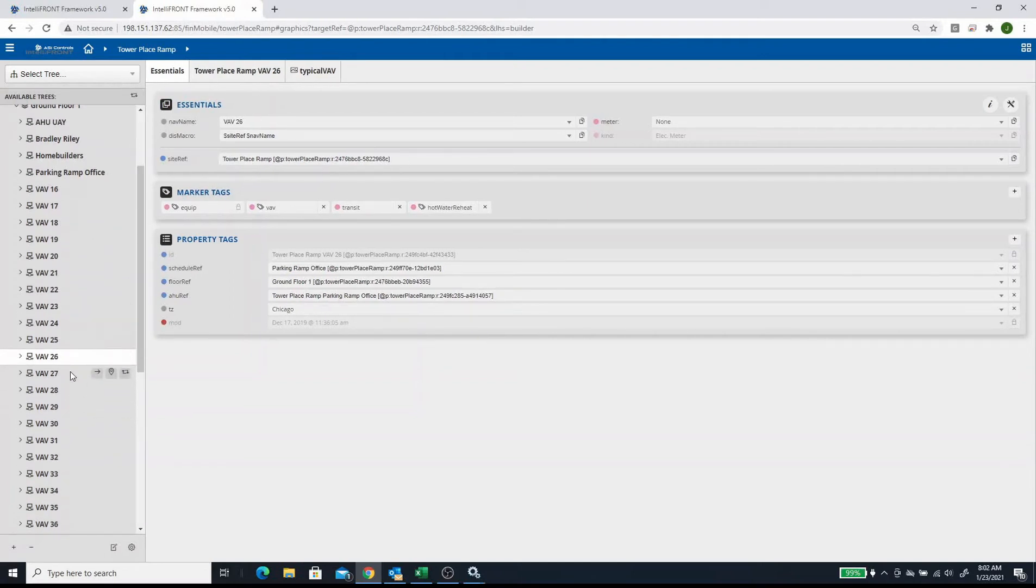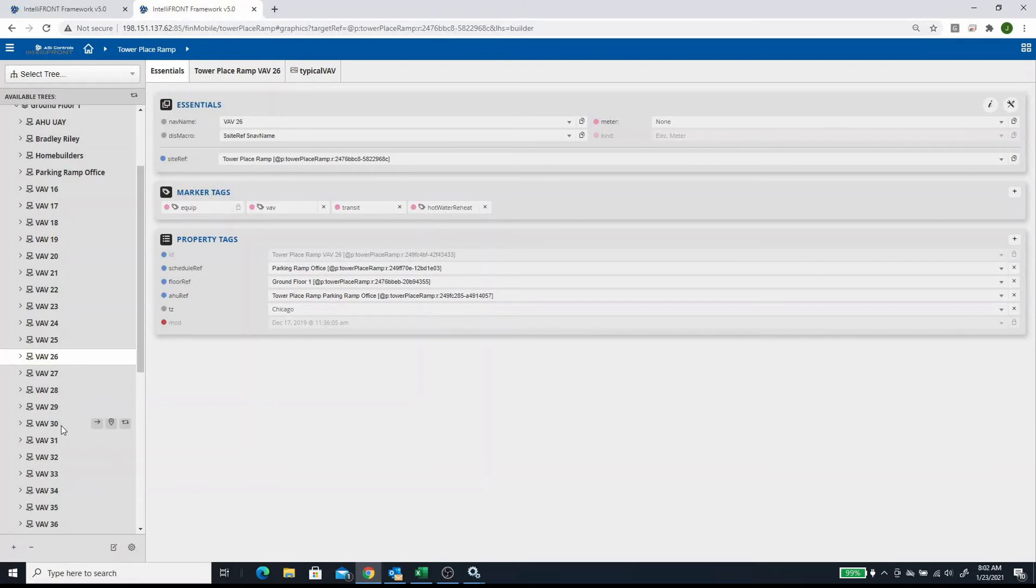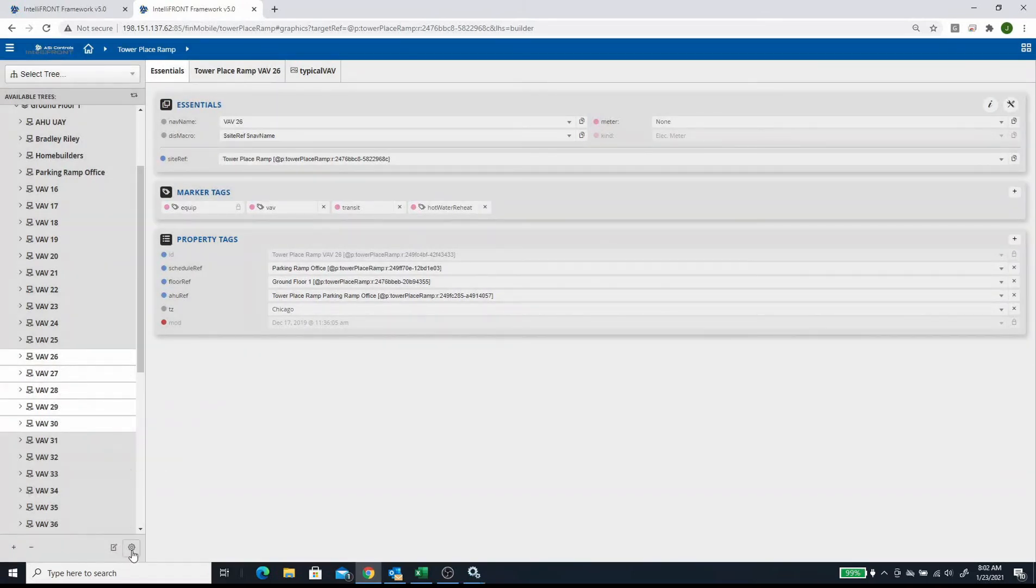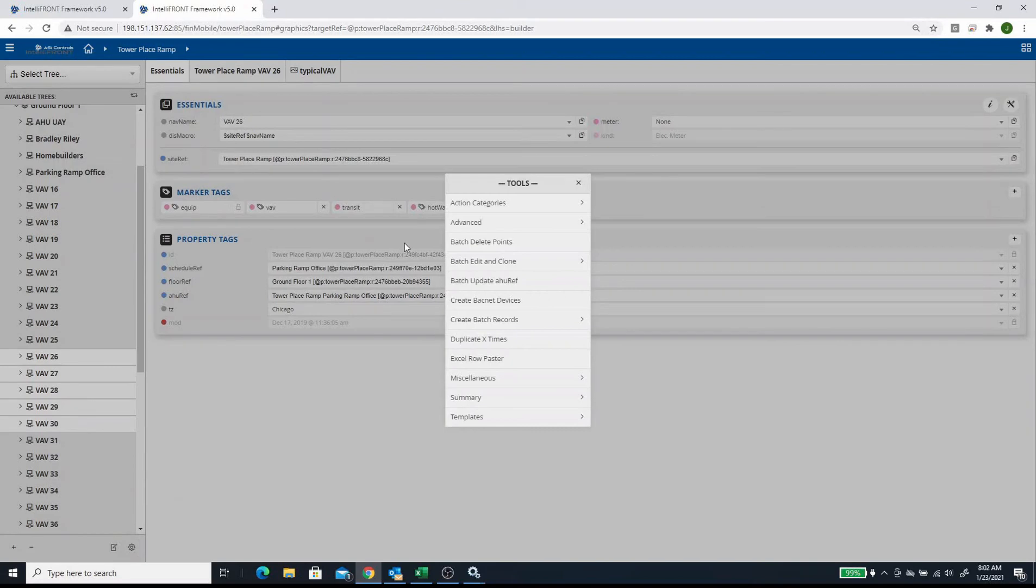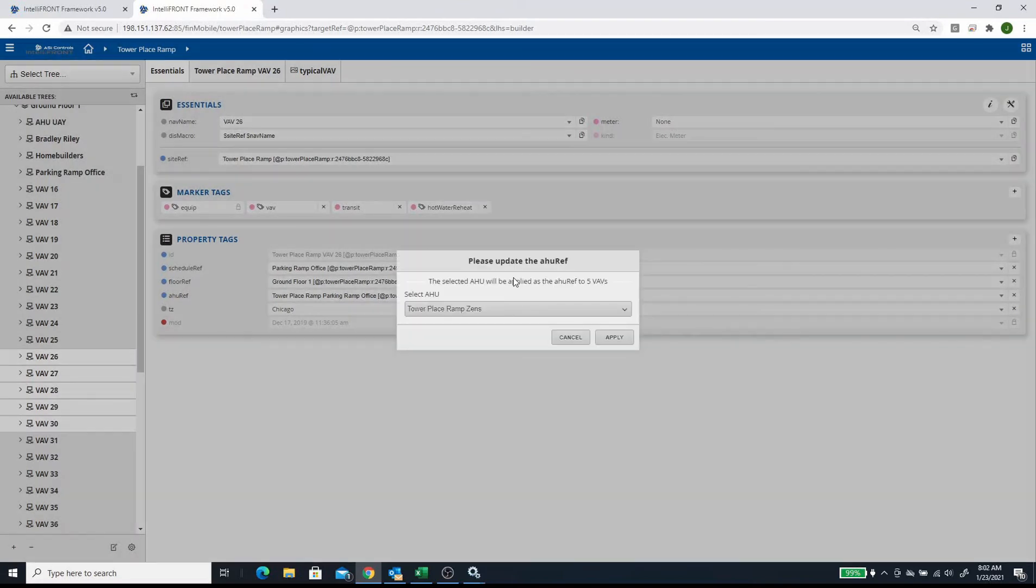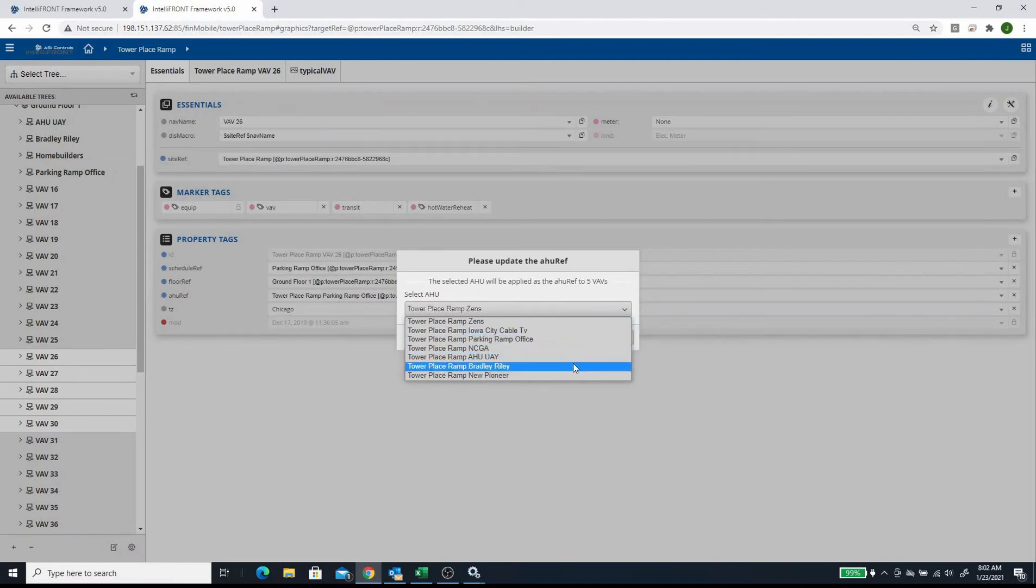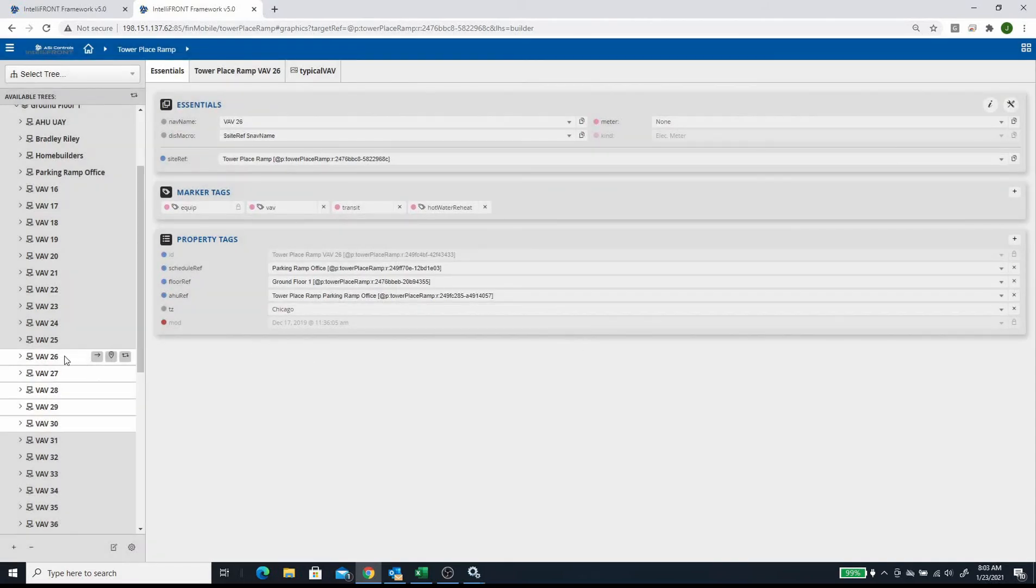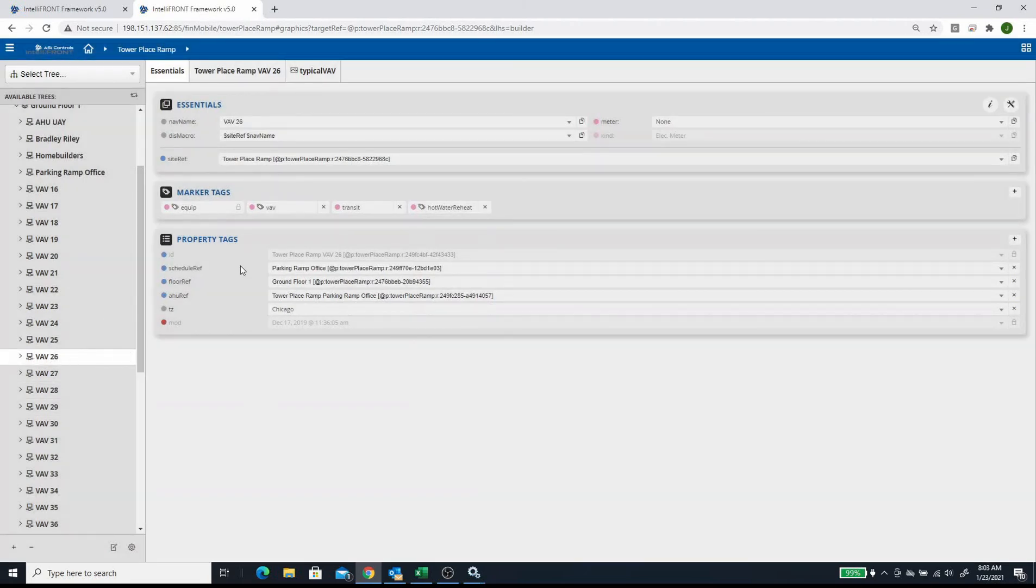So if you have four or five of them, you can just hit Shift and do the ones you have, or you can do Control and select them. Then you go to your Tools menu, go to Batch Update AHU Ref, and then you pick your air handler. That would automatically add that reference. This one's already been done, so you can see that the air handler reference is the Parking Ramp Office.